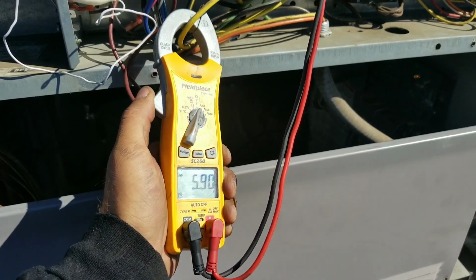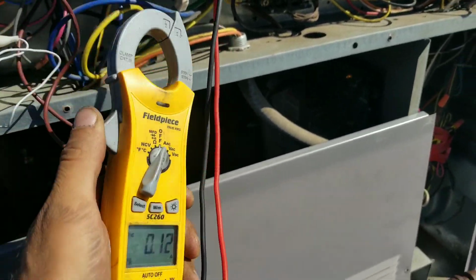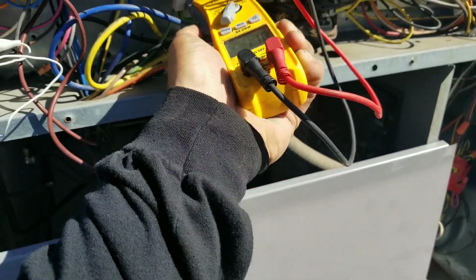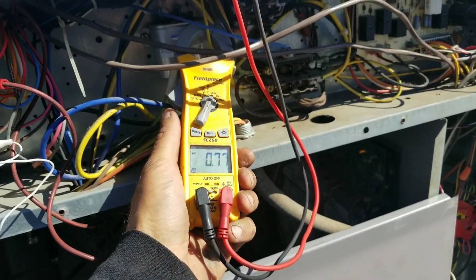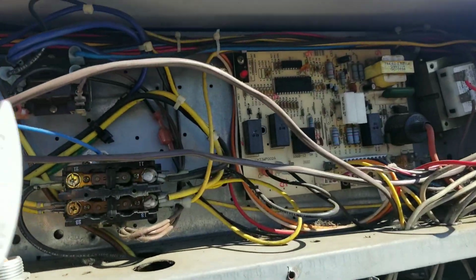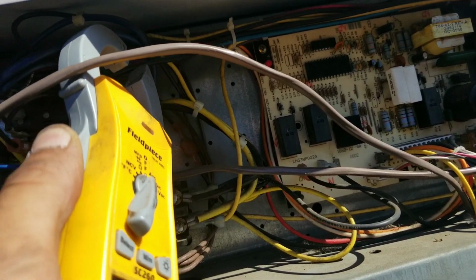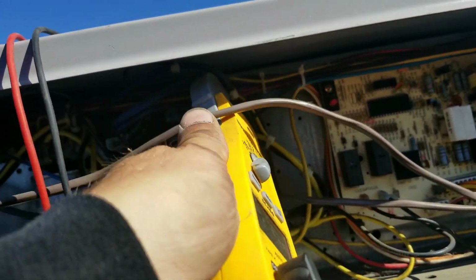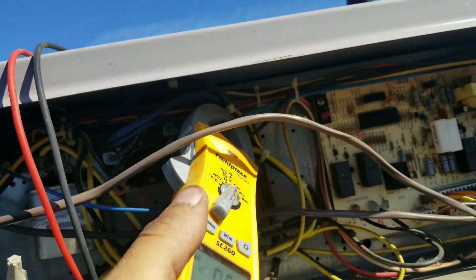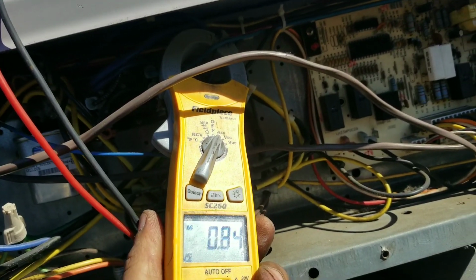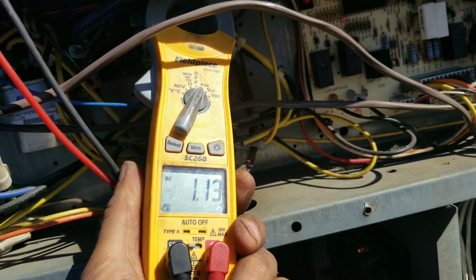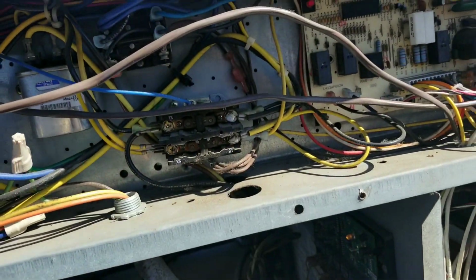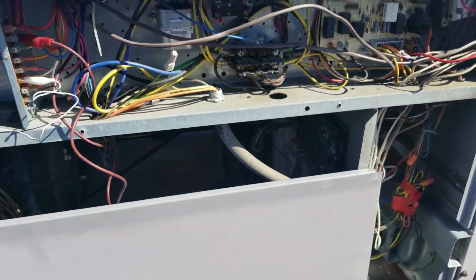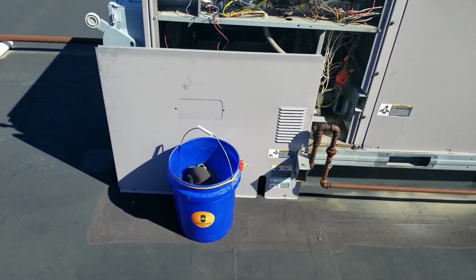See, my condenser, 5.9. Actually, that's not my condenser. .7. See if we can get up here to our blower motor. Come on. Go. Blower motor's pulling 1.1. Nothing out of the ordinary.